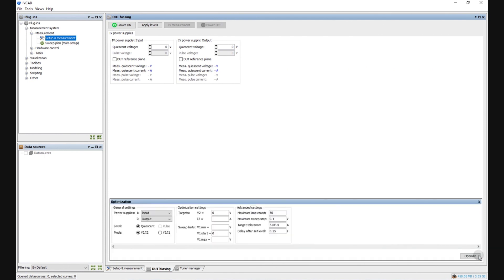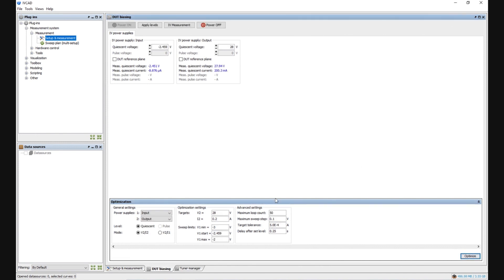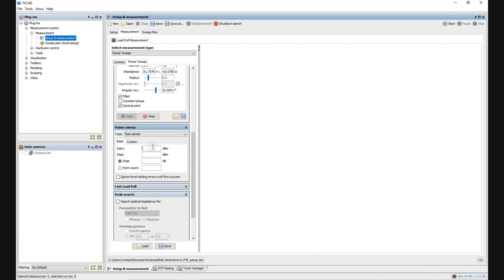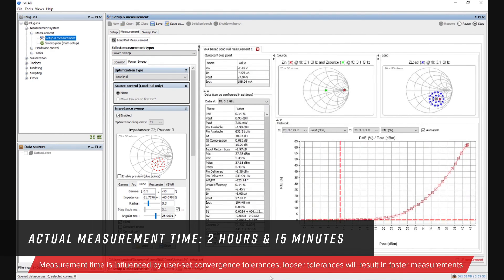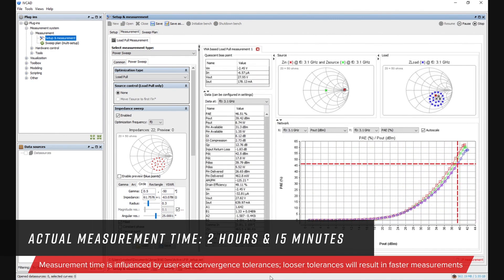Then we bias our device. In this demonstration, a bias optimization feature is used, allowing us to automatically set the device quiescent bias point. After that, we define the desired load impedance pattern that will be presented to our device under test, configure the drive power, and start the measurement. During the measurement, all device parameters are computed in real time, listed in the table on the left-hand side of the measurement window, and plotted on a Cartesian chart.